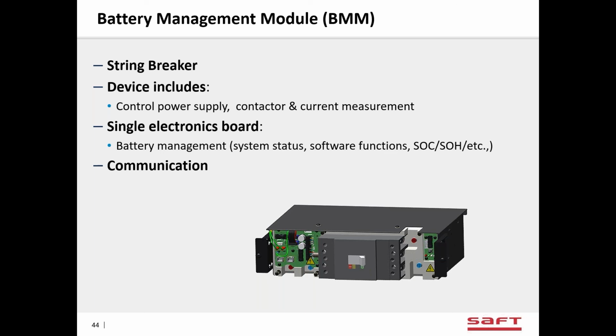The other interesting thing about this module is that inside it we have a DC to DC converter that goes from the battery voltage to the control voltage. So we generate our own 24 volts to run all of our battery management system inside this unit. This is different than our competitors where you have to run control power also to the battery. So that makes the battery installation much simpler, especially if you're replacing a lead acid battery where you don't need any control power and you don't have it available in your battery room. Flexion doesn't need it. It makes its own.